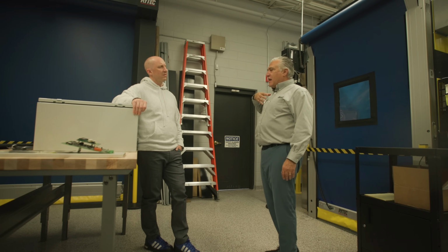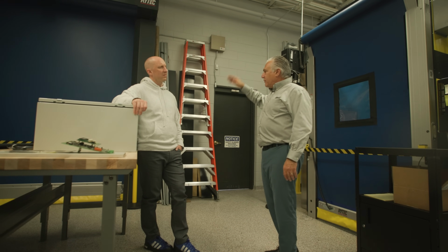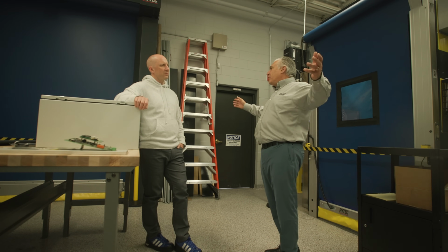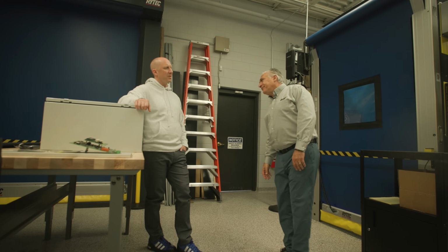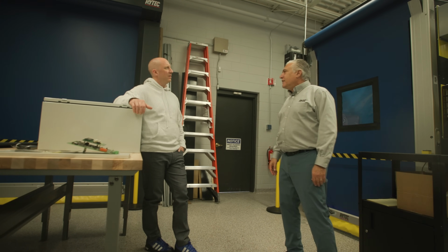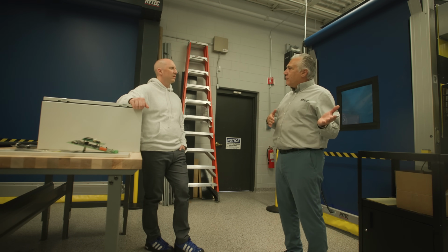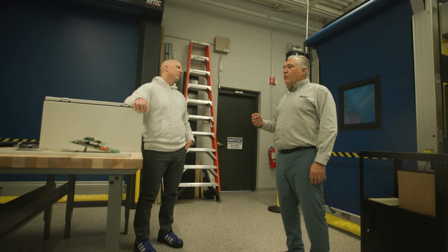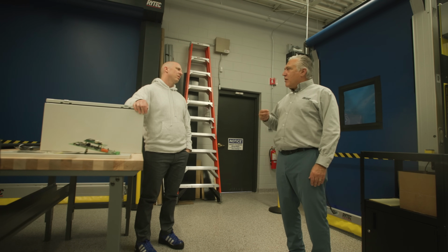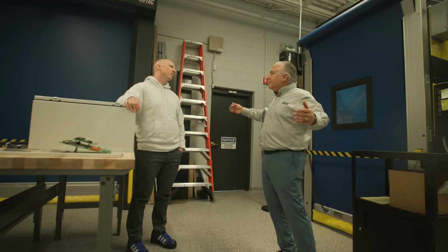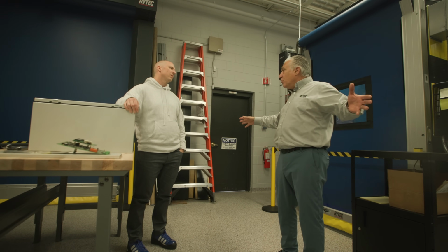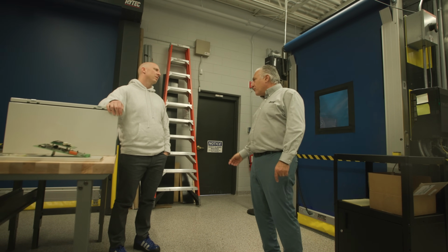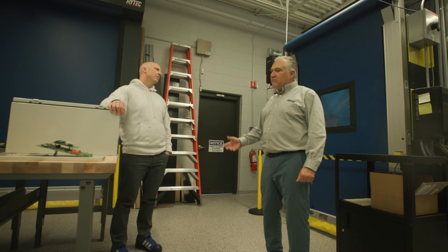Now in our world, that door is expected to do that repeatedly, 200 or 300 times in the first part of the day. You're heating up your supply line, and everything's getting hotter and hotter because the lower the voltage, the higher the current. Current is heat. So we're comfortable with 230 volt single phase. Again, some of the bigger doors, no, but in general, your typical garage or vehicular traffic door is going to be fine.